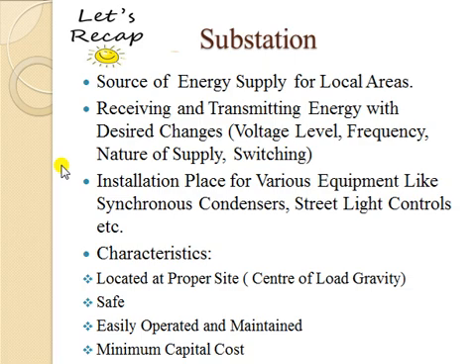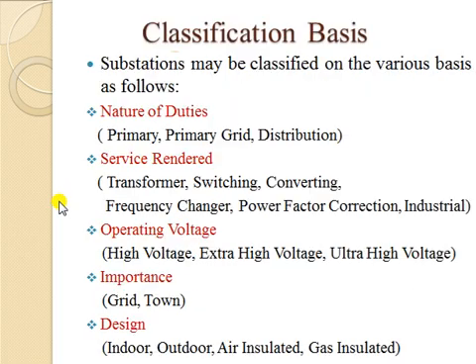What are the characteristics? You have to choose a proper site for a substation, and the most economic site is at the center of load gravity. This is not a geographical center — you place the substation such that all loads are at an equal distance from it. Substation operation has to be safe, should be easily operated and maintained, and must have minimum capital cost. This is a very important requirement.